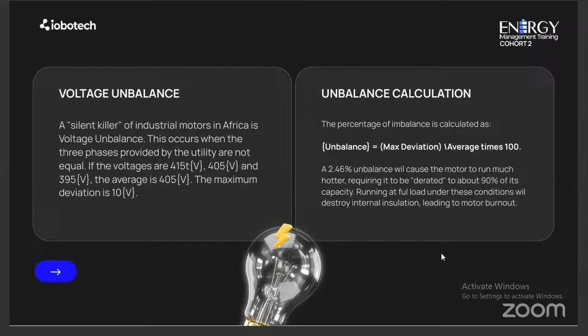Unbalance calculation. The percentage of imbalance is calculated as unbalance equals max deviation over average times 100. A 2.46% unbalance will cause the motor to run much hotter, requiring it to be derated to about 90% of its capacity. Running at full load under these conditions will destroy internal insulation, leading to motor burnout.